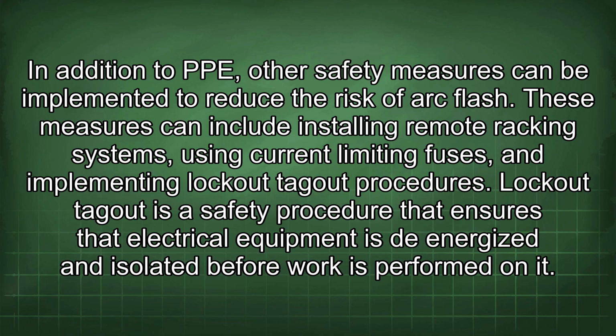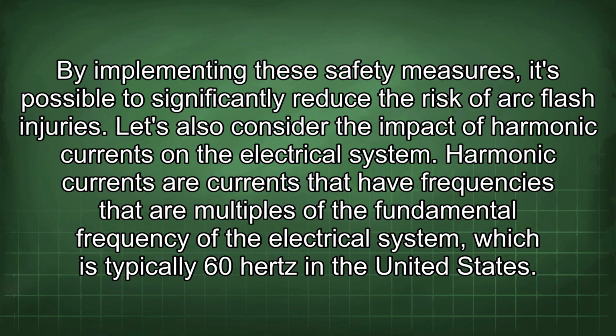Lockout-tagout is a safety procedure that ensures that electrical equipment is de-energized and isolated before work is performed on it. By implementing these safety measures, it's possible to significantly reduce the risk of arc flash injuries. Let's also consider the impact of harmonic currents on the electrical system. Harmonic currents are currents that have frequencies that are multiples of the fundamental frequency of the electrical system, which is typically 60 Hz in the United States.